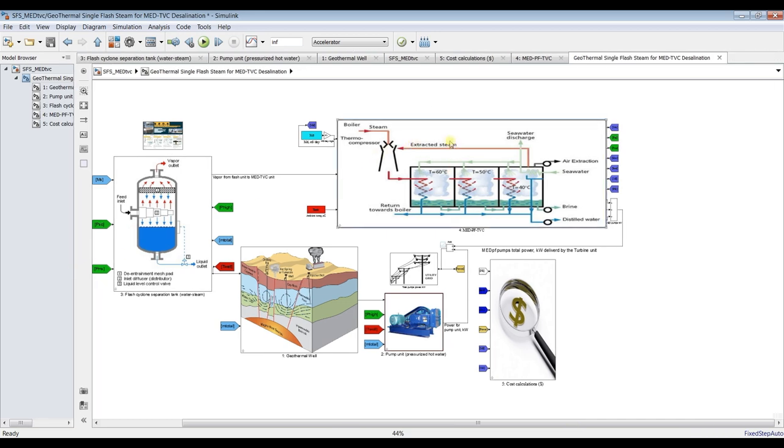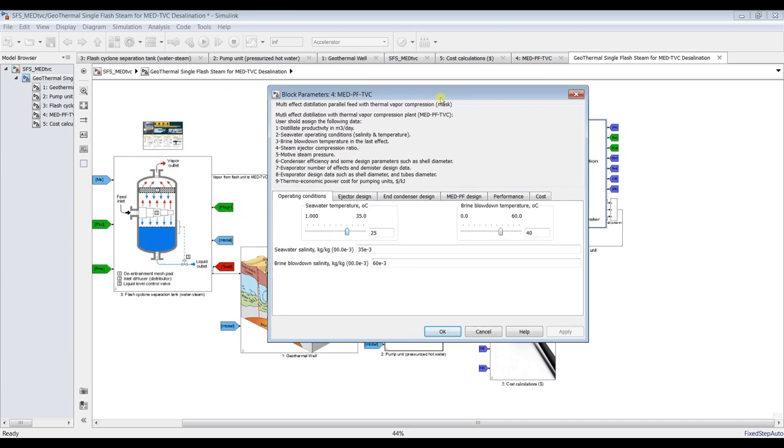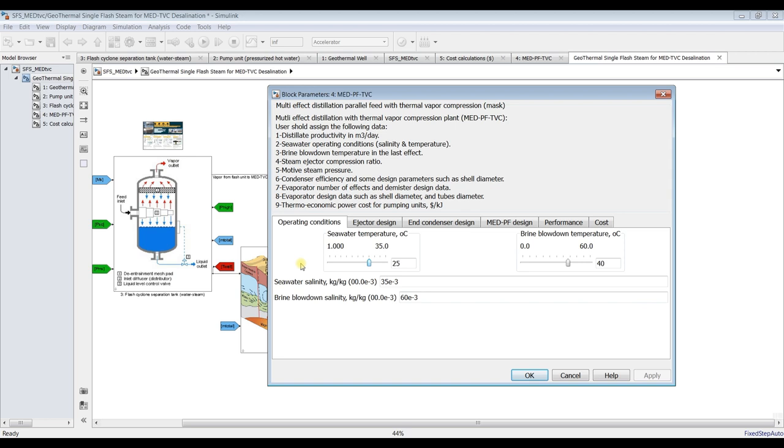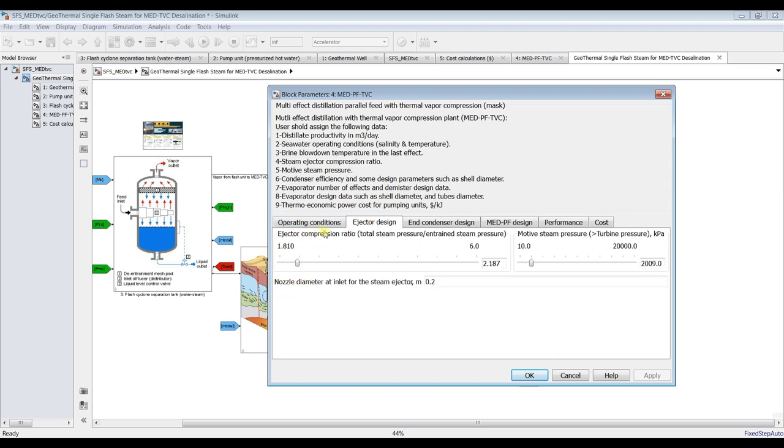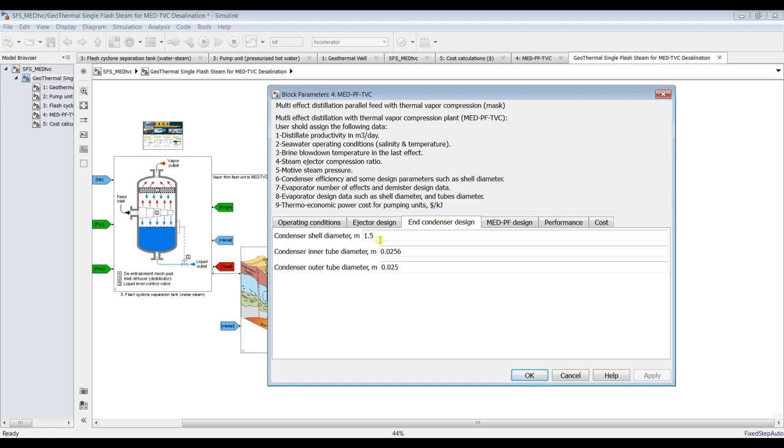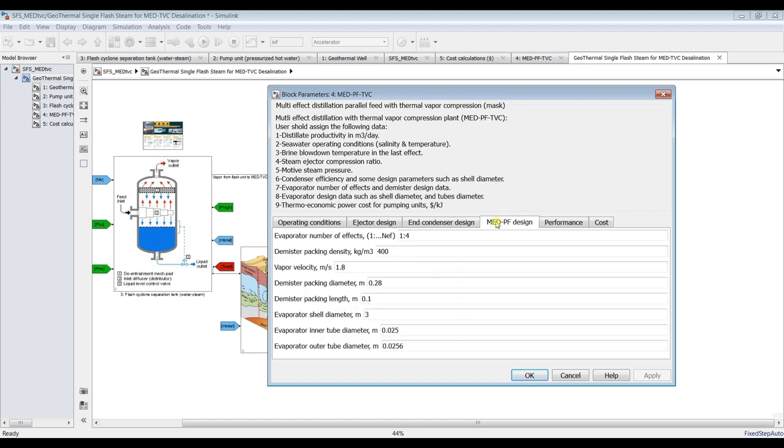Let's double click on MED. We have here seawater temperature. Suppose it's around 20 degrees Celsius. And ejector design. We have salinity. Suppose I'm going to use salinity around 35,000 ppm and the blowdown salinity is around 65,000 ppm. This is the ratio kilogram per kilogram. For steam ejector, you can assign ejector ratio and motive steam pressure. Important parameter in kilopascal. And condenser we can assign tube diameters. Number of effects, suppose I'm going for six effects.